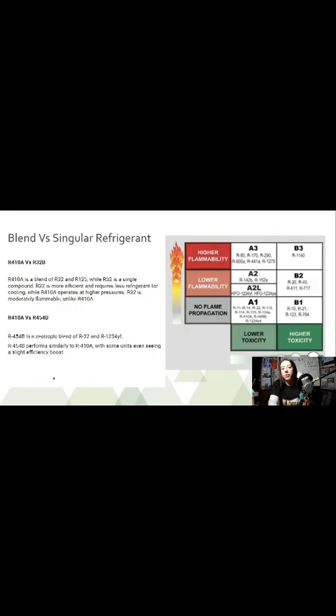So blend versus singular refrigerants, okay? Zeotropic versus azeotropic, for those of you science heads. We have 410A as a blend of R32 and R125. R125 is that flame suppressant I'm talking about. R32 is a single compound, so it's not a blend. R32 is more efficient and requires less refrigerant for cooling, while R410A operates at a higher pressure. R32 is moderately flammable, unlike 410A. 410A will not burn. I mean, anything will burn if you heat it hot enough, but in a typical situation, it will not burn.